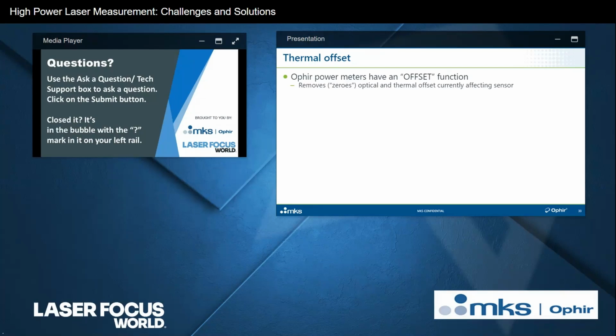It's important to use that offset button to zero the sensor's background offset only when the sensor is in thermal equilibrium with its environment. For example, let's say you bring the sensor in from a hot car into an air-conditioned lab. You connect it to a meter, you turn on, and even before you turn on your laser, you look at the meter and you're going to see a reading. Actually, you're going to see most likely a negative reading, because the sensor is hotter than its environment. So heat is now moving from inside the sensor outwards into the surrounding air. And that heat flow is going to be picked up by the sensing element on the disk.